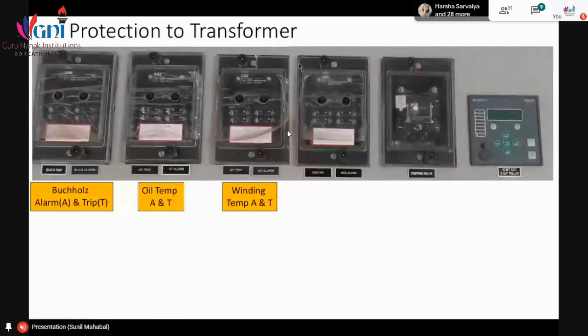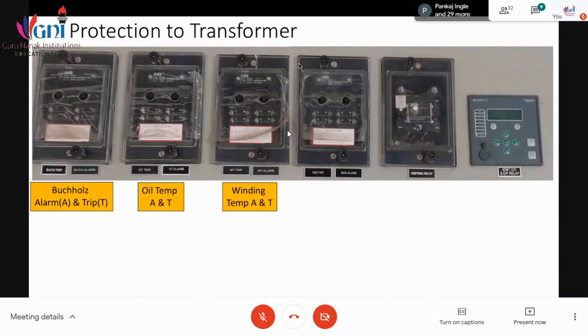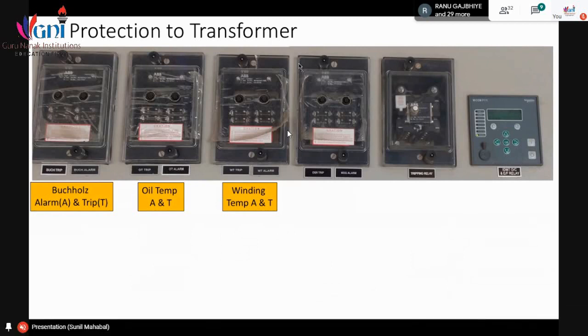Then there is the oil surge trip. Why is this oil surge relay provided? It is provided between the online tap changer, OLTC, and the transformer. During online tap changing, there is a possibility of a huge spark, and that spark may convert into mechanical energy, and the oil may surge into the tank. If it surges beyond some level, then this OSR will trip. There is no OSR alarm, there is only OSR trip. If the OSR operates, then it is not healthy for the transformer, and it safeguards the OLTC also if it trips.